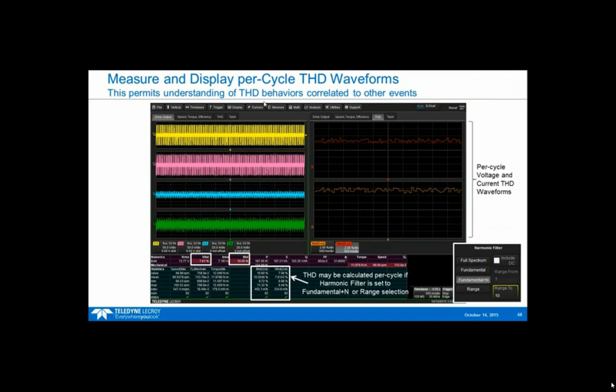This is additional capability we're launching in the next week or two. This is a harmonic calculation capability, which includes harmonic filtering on the drive input and drive output. In this case, we selected fundamental plus N, applying a harmonic filter to these calculations, looking at the fundamental through the 10th harmonic. Once we know what the fundamental is, we can establish the total harmonic distortion. We can measure total harmonic distortion as a mean power or mean value parameter in this table, highlighted here, for both voltage and current. We can also do it for power. I can get a value for 82 different calculations.